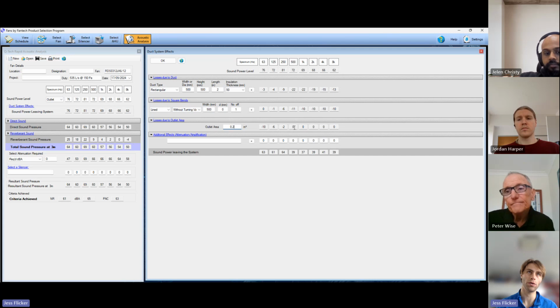So more end reflection means you have less sound entering the space. Correct, yeah, so you actually want that. Also be aware, and we'll talk about this a bit later, but on a supply air system you generally have a lot more outlets than you do on a return air ductwork system. And the sound power is distributed to all the outlets - it doesn't just go to one, it's distributed through the whole system.